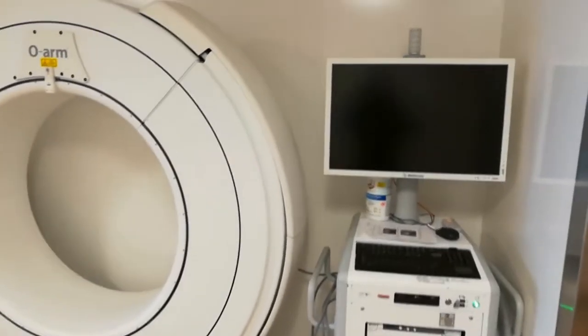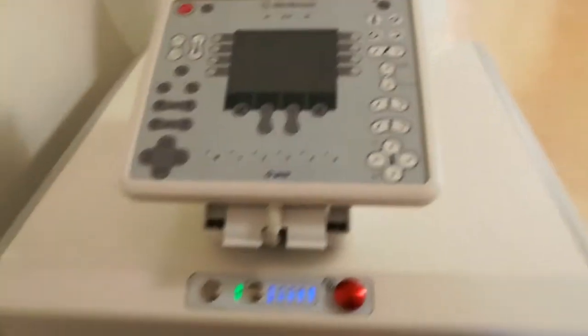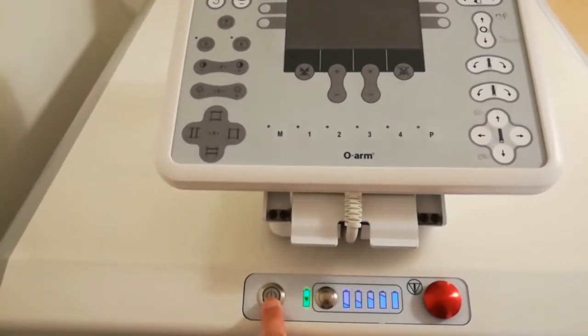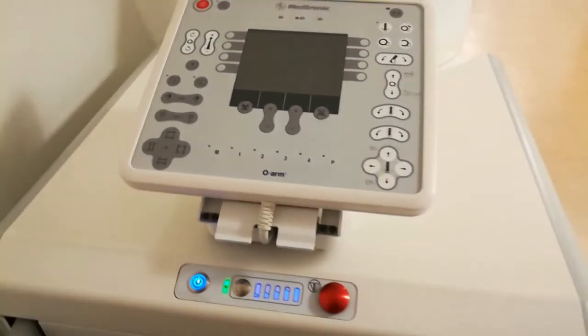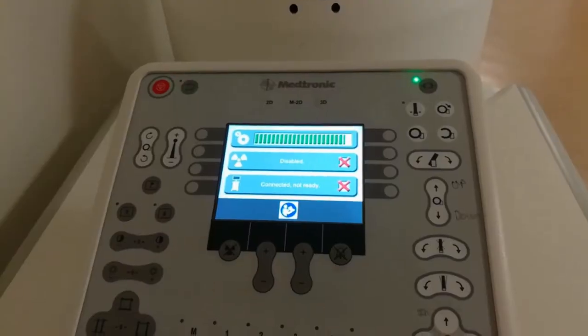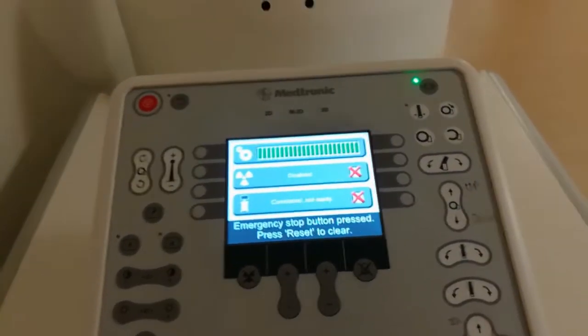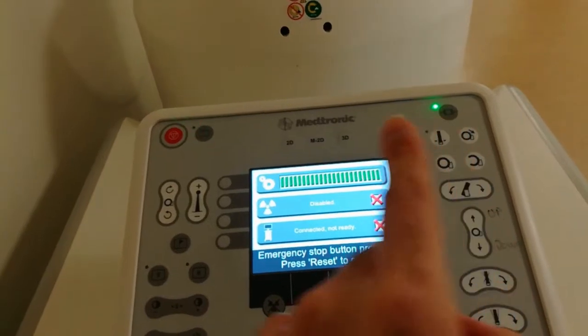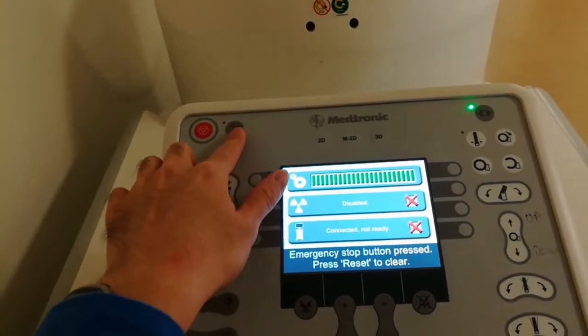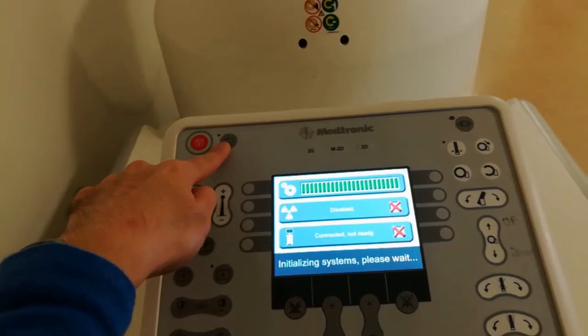So for starters, we're going to power up the actual O-arm portion so we can actually drive it, because right now it's dead. So power it on, we hit the power button, press and hold. There you go, and then just wait a sec. Alright, so upon booting up of the O-arm, the brakes are automatically going to be engaged. So hit the alarm reset button, that'll disengage the brakes, and you can actually drive this thing around now.